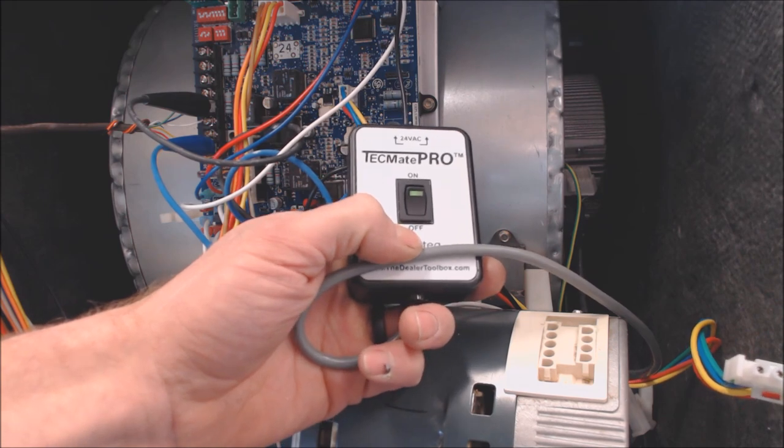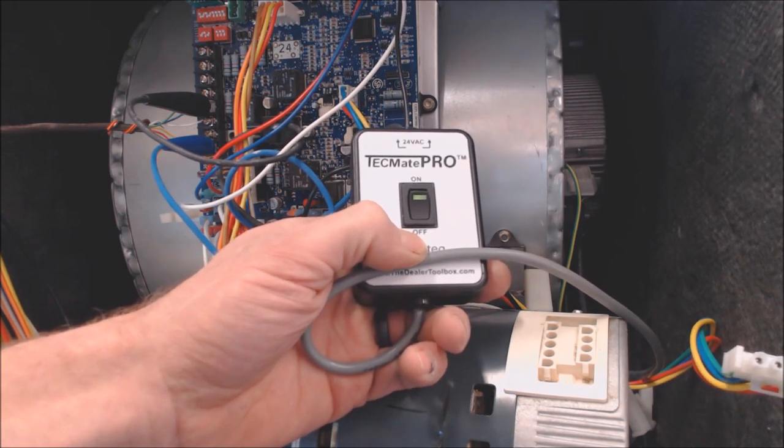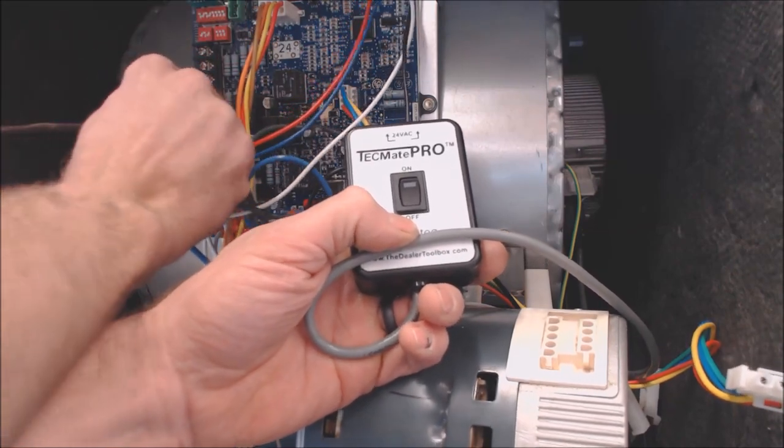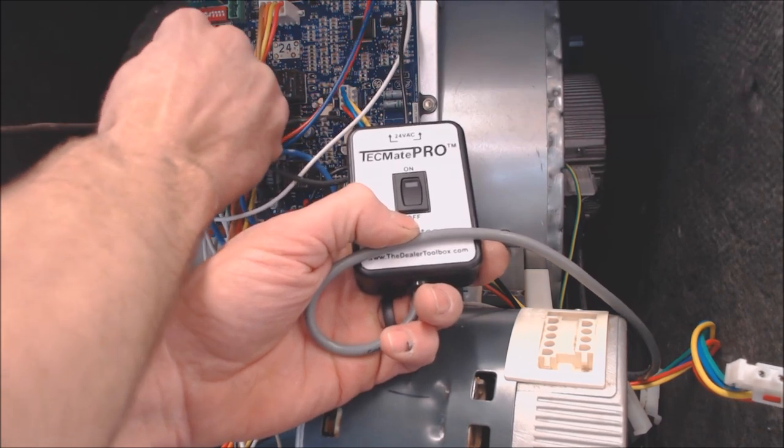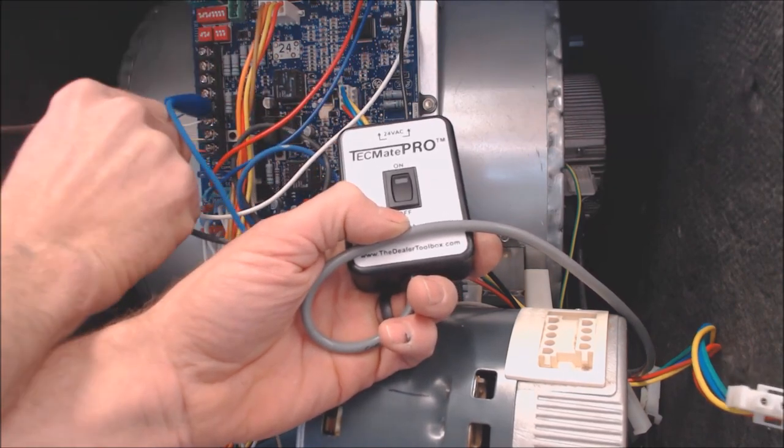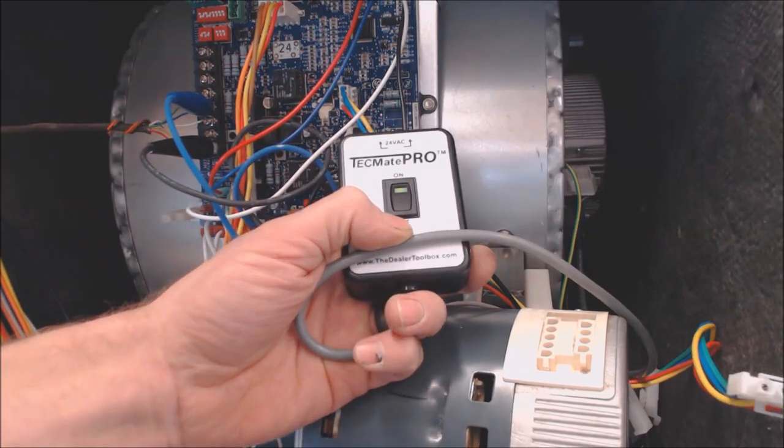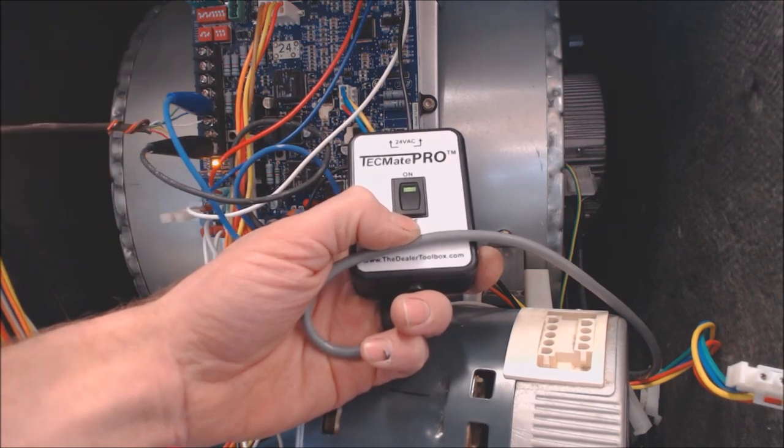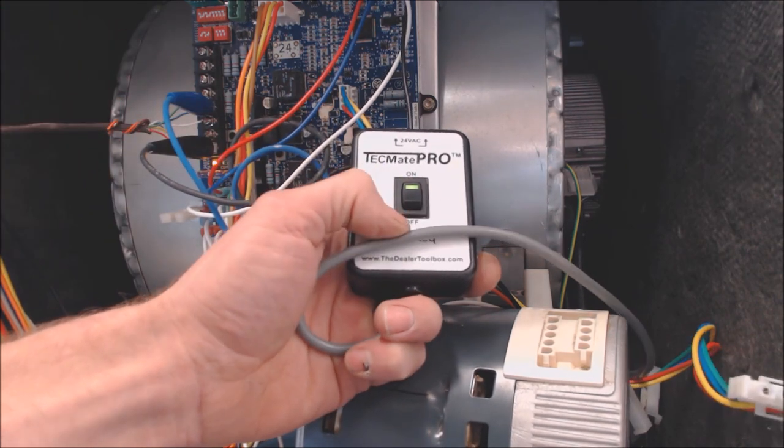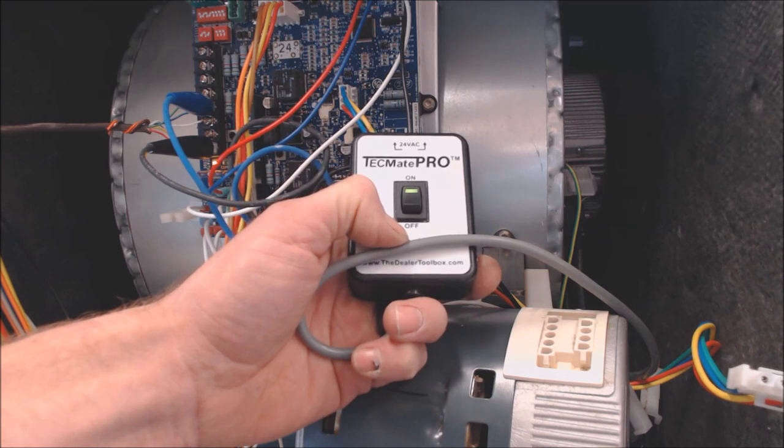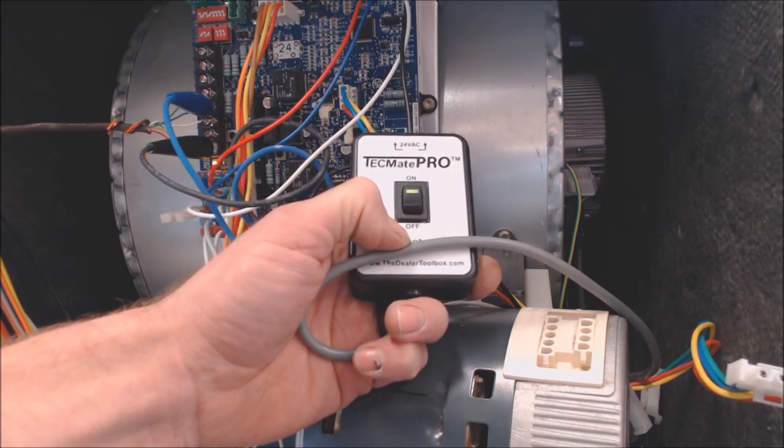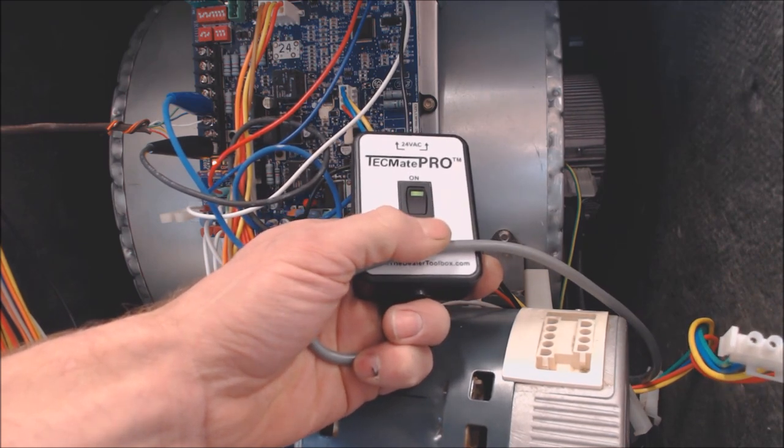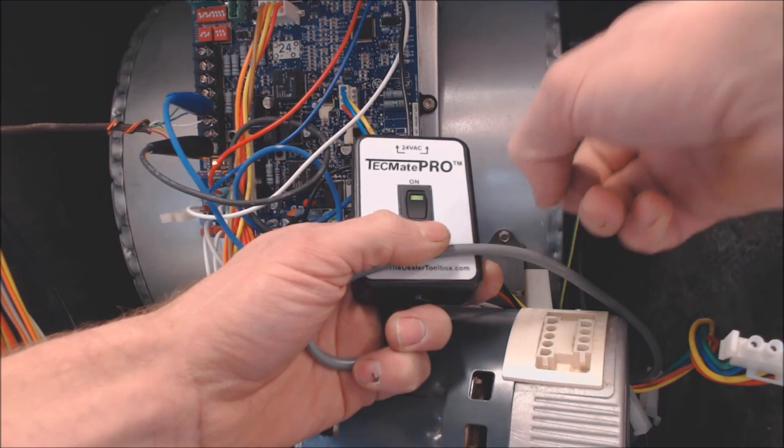All right, so we've effectively checked the variable speed blower motor. We're going to now turn the power off. I'm going to switch these two connections. We're now going to turn the power back on again. I flip these two between common and power. And now I'm going to turn this on. And it's going to test the variable speed blower motor the same way.